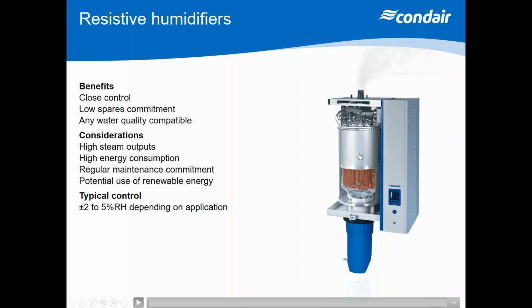Also, with a resistance heater such as this one, you have inbuilt scale management. So as scale forms on these heating elements, as the element expands and contracts, the scale will crack and fall off and be collected into the scale collector at the bottom of the unit, which periodically can be drained down, emptied and put back by the maintenance engineer. So we're never having to buy another plastic cylinder. I've still got to maintain the unit, but I don't have such high spares costs. So with a resistance heater, we're going to get that close control.